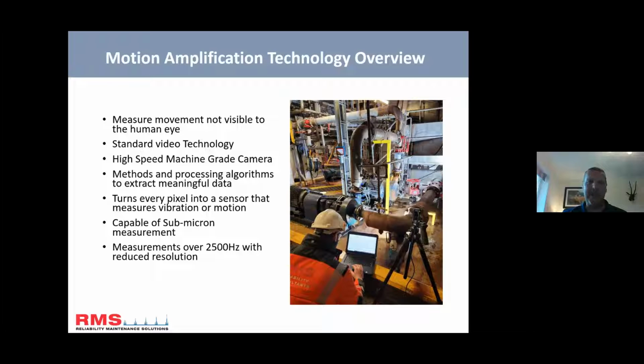It's all to do with light - as something vibrates, the light changes, and that's what these systems are able to pick up. So it's measuring the photons of light within that pixel. We can do submicron measurement, and I've seen examples, and done some quite high frequency ones, well over 2,500 hertz. You can go even a lot higher than that, but because of the camera's native displacement unit, displacement drops off with higher frequencies.